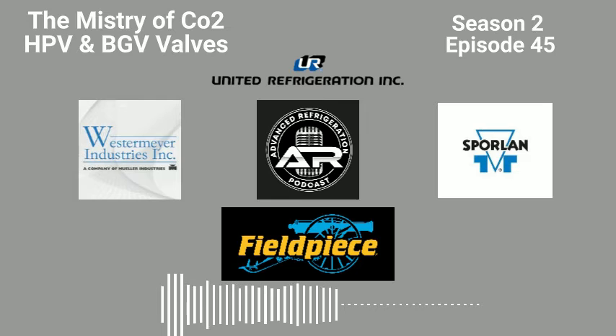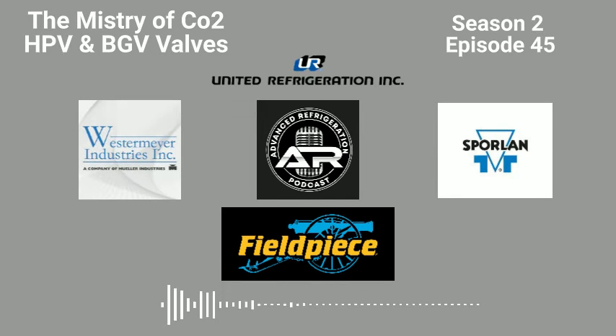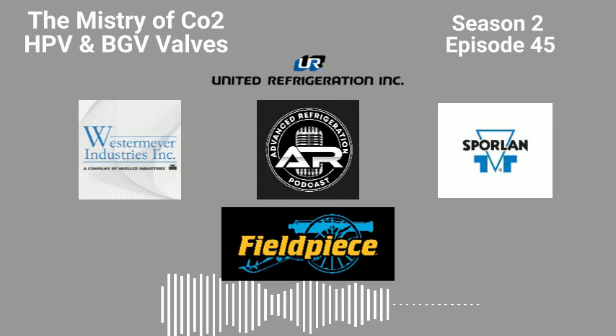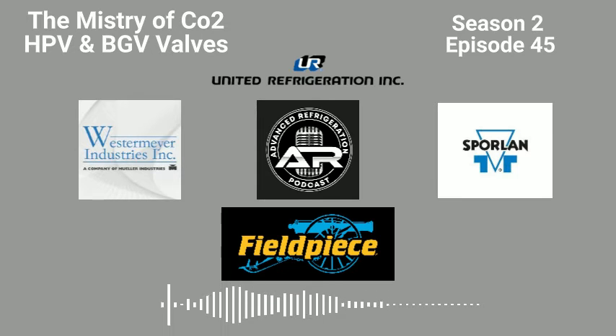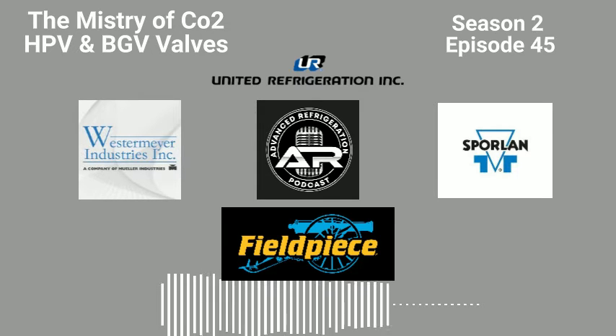So we'll go over why do we need this. Okay, so we've gone over in other episodes how CO2 works. I'm not going to super deep dive into that, but why do we need these valves? Why is this different than normal refrigerant? So CO2, when it gets above 87 degrees condensing temperature, it no longer has a PT relationship, meaning it no longer shares a pressure temperature relationship. So as the pressure goes up above 87 degrees, that relationship no longer is a linear line. It could be anything. It's an unstable fluid.